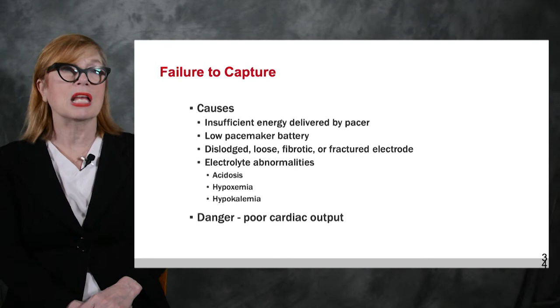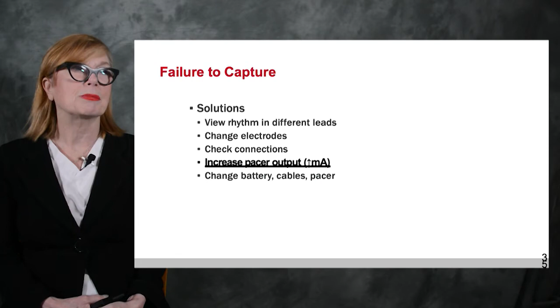First thing we're going to do is call, ask permission to increase the mA, or have the physician or APP with us and have them increase the mA, but you must increase the mA with failure to capture. Okay, so remember what I said before: always look at least 2 views, change your electrodes, check your connections, make sure you're all connected, increase your mA, change your battery, change the cables, and ultimately change the pacemaker.